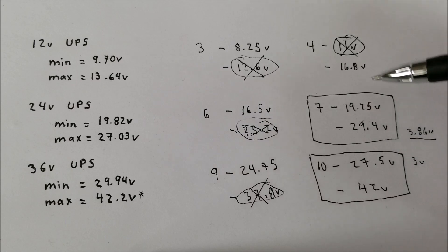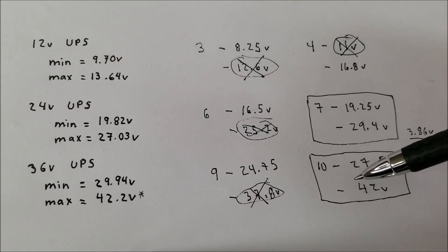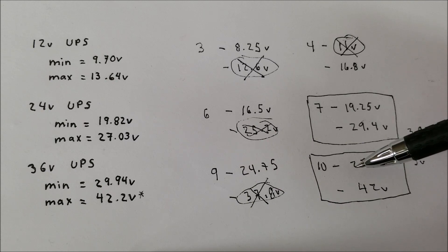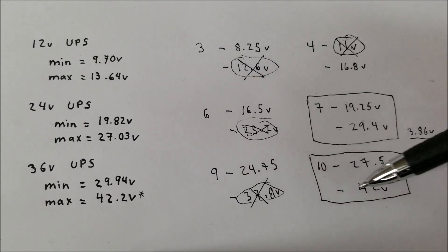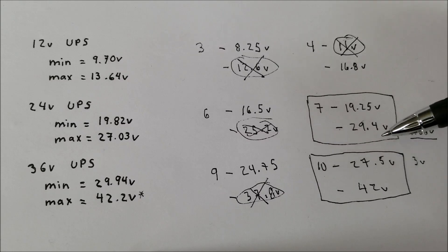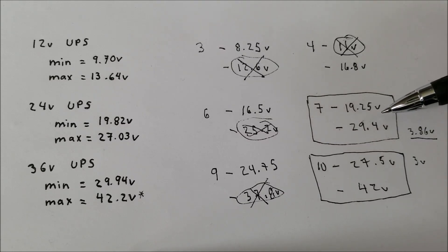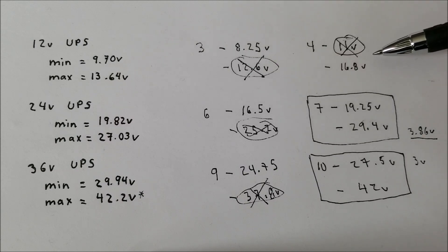So from these three battery combinations, I think the best solution or the best unit to use with lithium-ion is the 36V UPS. The second best obviously would be the 24V UPS and obviously for the 12V, there is no possibility of running it with lithium ion.